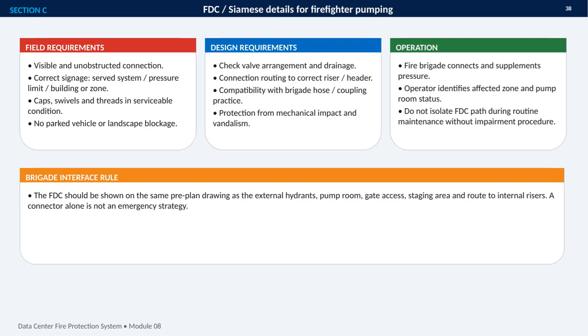This section focuses on the FDC, or Siamese connection, and how it supports firefighter pumping during an emergency. The first priority is field readiness. The connection must remain visible and unobstructed, with clear signage identifying the served system, pressure limit, and building or zone. Caps, swivels, and threads need to stay serviceable, and access must not be blocked by parked vehicles or landscaping.